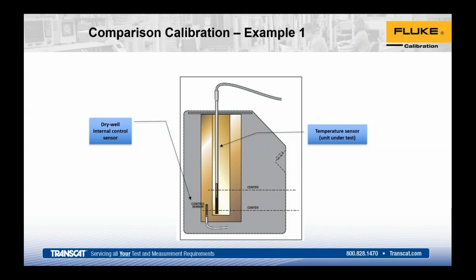So in this example, let's assume that the dry well is 0.25 degrees C accurate to the control sensor. The unit you're testing would probably have a spec close to ±1 or greater, and that would be appropriate.